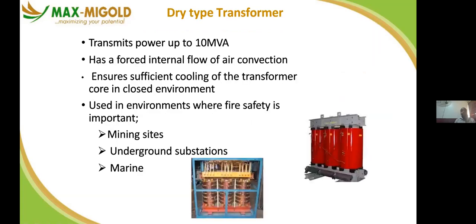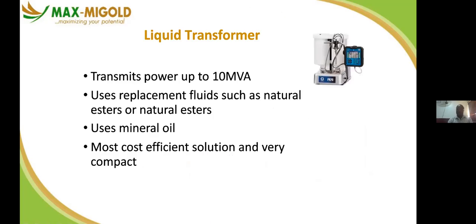We have dry type of transformer. In most cases, like in an enclosed environment where it's airtight, what you need there is this dry power transformer. So they don't need oil, they don't need anything, they are just there. What you need is just cooling. You provide cooling for such transformer because they emit heat as they are working. So they are called distribution transformer. They are used in high-rise buildings to distribute load, power demand from one floor to another. So in all those high-rises you see on the island or in the mall, you will see these transformers there because they are airtight. We have the liquid transformer. This is not common, though it exists.